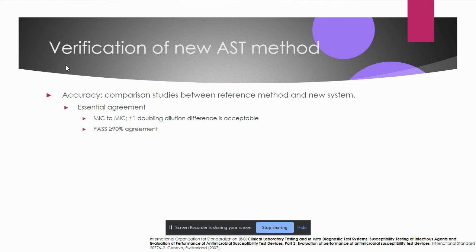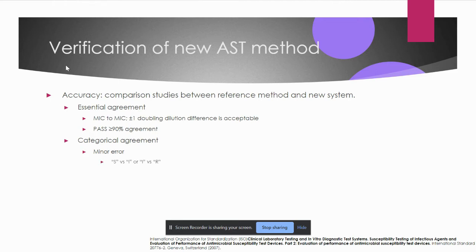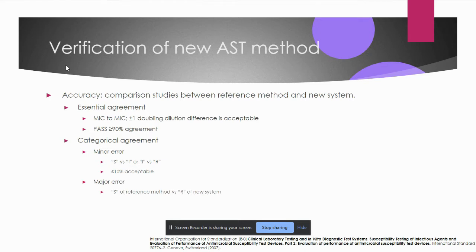To pass the verification study, 90% or more of MICs should be in agreement. Next, we assess categorical agreement — the agreement between interpretations such as susceptible, intermediate, resistant, or susceptible dose-dependent. Minor errors are susceptible versus intermediate or intermediate versus resistant results, and 10% or less is acceptable. A major error is when the reference method gives susceptible but the new system reports resistant — meaning a falsely resistant result is reported to the clinician and a suitable antibiotic may not be used.